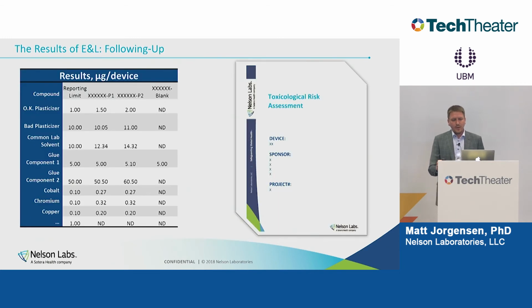Okay, so once you've done all of this evaluation, this chemistry work, whether you have a regular permanently contacting device or this chemistry with a gas path device, what do you do after that? All of this should be followed by a toxicological risk assessment. I have to mention this because it's a critical step. It won't do to just do the chemistry testing. The FDA won't really accept just raw chemistry results as part of this.